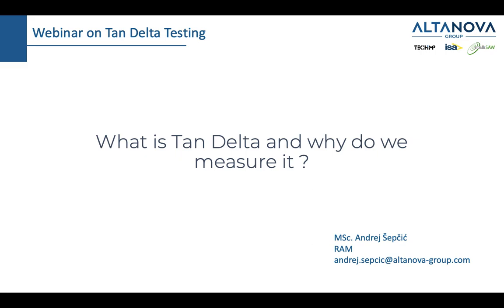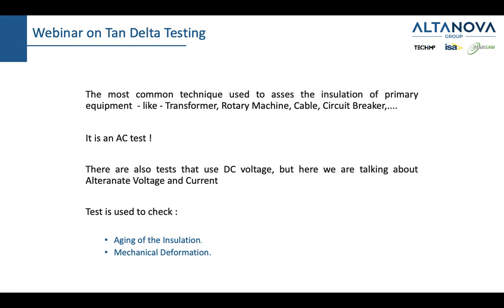It's okay? Okay. So, what is tan delta and why do we measure it? Tan delta is, as we said, the most common technique used to assess the insulation of primary equipment like medium and high voltage transformers, but also current and voltage transformers, rotary machines like generators and motors, also medium and high voltage cables, circuit breakers, surge arresters, all types of primary equipment. Let us say anything that has an insulation can be tested using this method. It is important to emphasize also that this is an AC test. It is not a DC test. An AC test means, of course, that we will not be using direct current or direct voltage. We will be using alternating voltage and alternating current. Of course, there are different methods, but today we will be focusing on an AC test. And this test is used to check aging of insulation and also mechanical deformation.